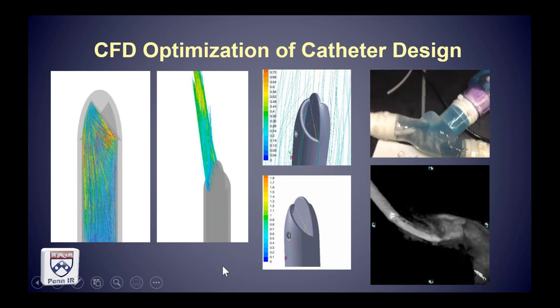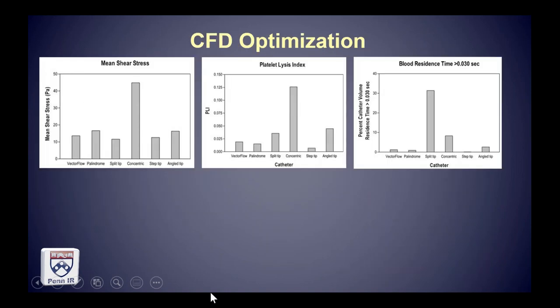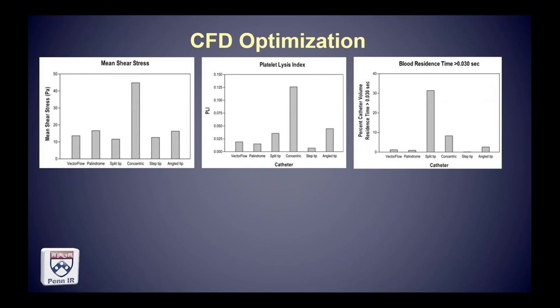This led to parameters used to optimize catheter characteristics. Changing the angle of the flow-deflecting interface of the catheter tip can alter these parameters by huge amounts. We looked at shear stress, the characteristic of causing platelet lysis leading to platelet activation and aggregation, and blood residence time — basically how long blood hangs inside the catheter — which is an independent metric of thrombosis risk. The catheter under development, the so-called vector flow catheter, was highly favorable in all of those parameters through this iterative computational fluid dynamics process.